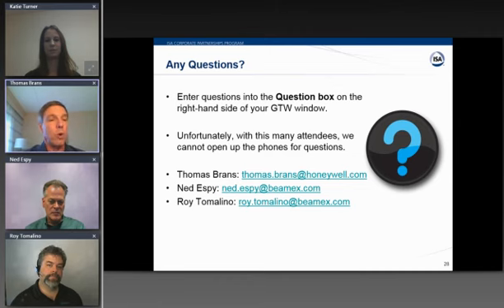But now with digital protocols, you can leave all that information in the digital form and send it out as a digital output, and that could be HART, it could be DE, it could be fieldbus, Profibus, and I suppose even wireless would be a digital output as well. When you did that last digital to analog conversion, of course there's error in something like a D to A, so when you take that out, you remove some source of error. And digital gives you a lot of other capabilities as well, such as being able to transmit diagnostics. You don't get that with analog. You can send out more than one variable, and there are just a lot of advantages to having digital communication.